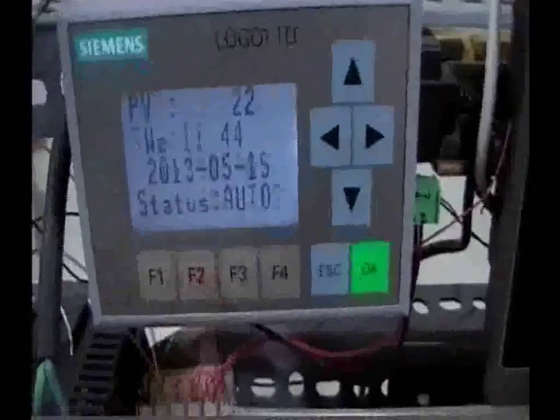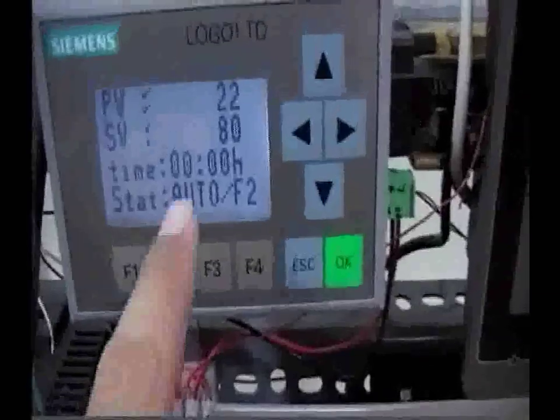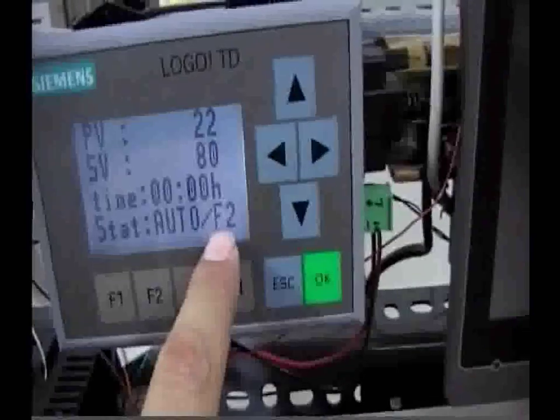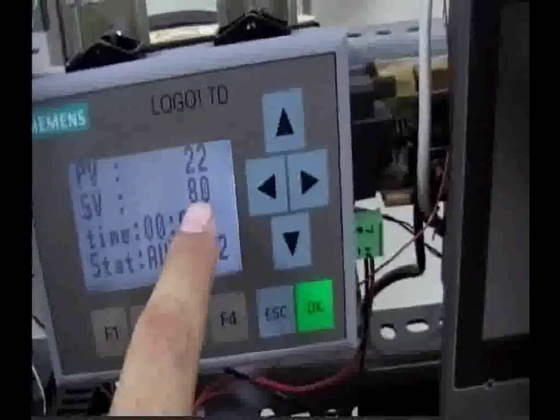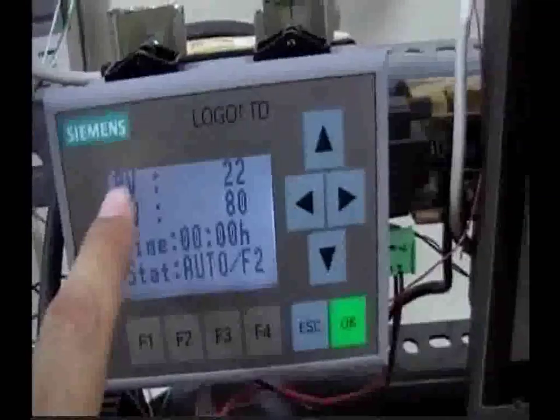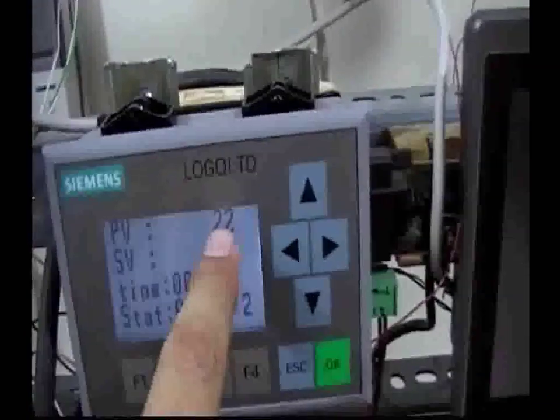Then to restart the system, start the system again, and this time push F2 function. This way you're going to see that the system is in auto F2 mode, and the curve says that it has to be 80 degrees, but the temperature on the sensor is reported as 22 degrees centigrade.